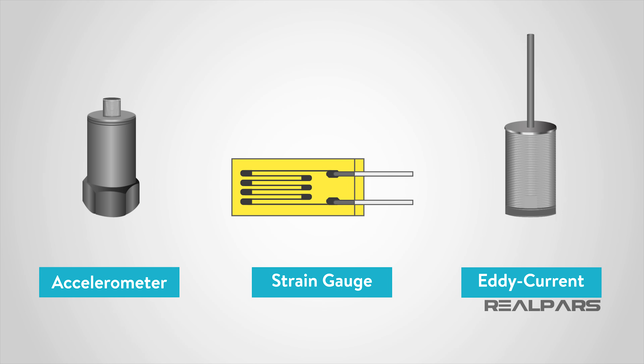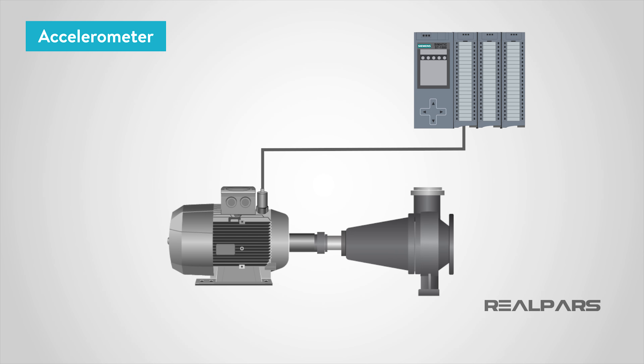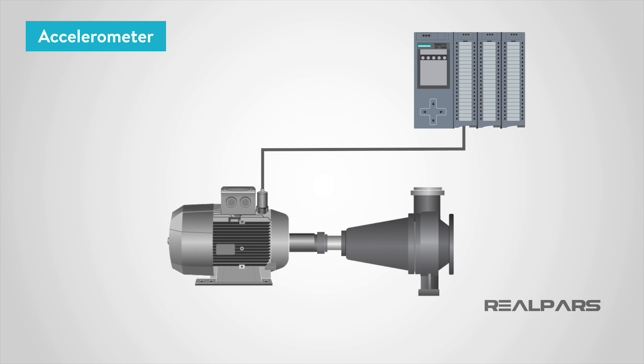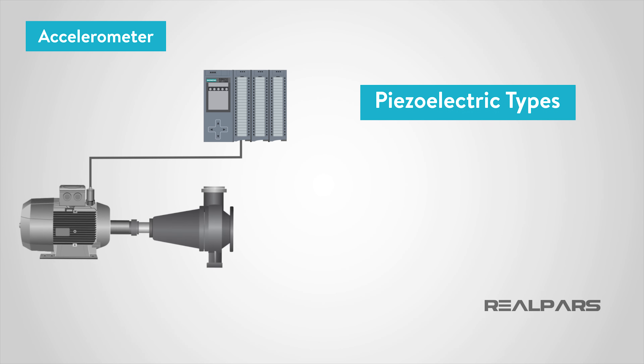Now that we know what vibration is, let's look at the different types of sensors to monitor vibration. First, we'll talk about an accelerometer. Accelerometers are devices that measure the vibration, or acceleration of motion, of a structure. They have a transducer that converts mechanical force caused by vibration, or a change in motion, into an electrical current using the piezoelectric effect. There are two types of piezoelectric accelerometers: high impedance and low impedance.